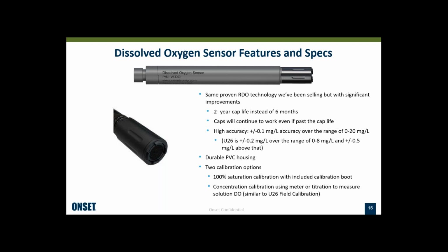The caps will continue to work even after the cap has reached its 2-year life, and the user just needs to check the accuracy, and as long as the accuracy is still good enough for their application, they can continue to use that cap if they like. The accuracy is also improved over our U26 loggers. With calibration, users can get plus or minus 0.1 milligrams per liter accuracy over the full range of 0 to 20 milligrams per liter, which is quite a bit better than the U26 logger, especially at the higher end of that logger's measurement range, where it lost some accuracy. So, better accuracy. It also has a nice durable PVC housing.